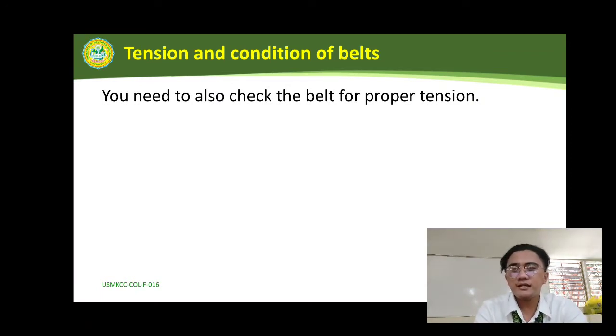If the belt is in satisfactory condition, or if replaced, the new belt should also be checked for proper tension. A new belt loses 60% of its tension in its first few hours of operation, so it needs to be tested under heavy load and retensioned after installation.